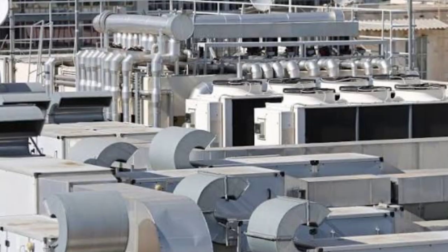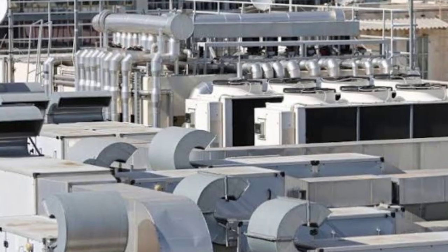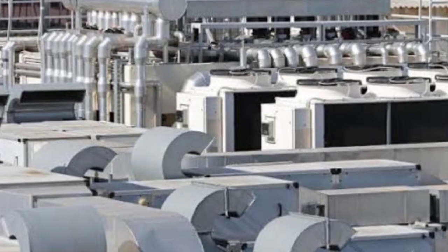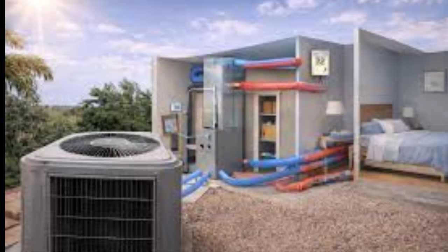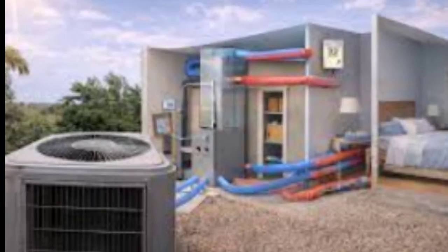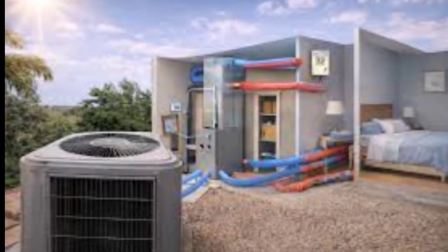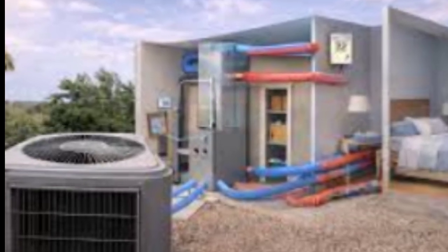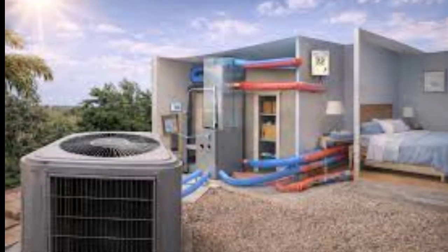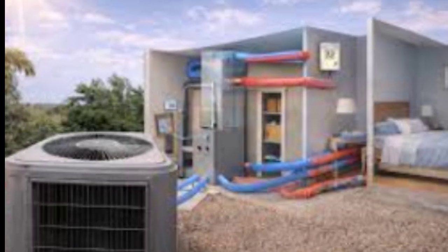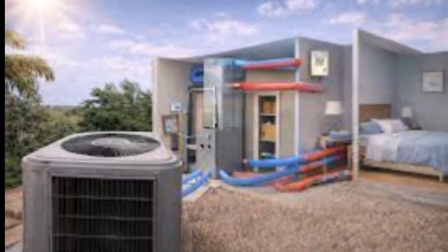Second, they think hard about ductwork. If flex duct is the only option, they make sure it's installed correctly: no kinks, no sags, proper support every 4 feet, all connections sealed with mastic, not just taped. But given the choice, many technicians will spend the extra money on rigid metal ductwork in critical runs, especially the main trunk lines. It costs more upfront and lasts decades longer.